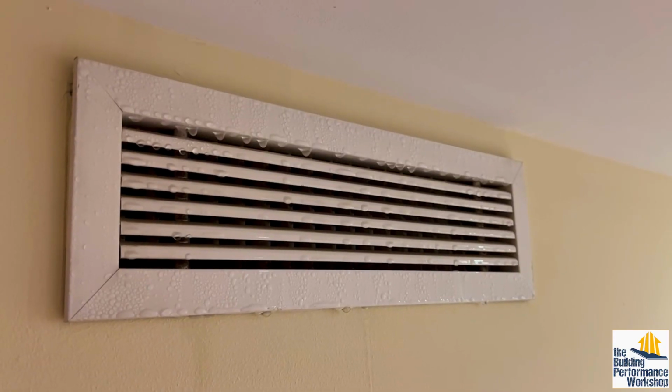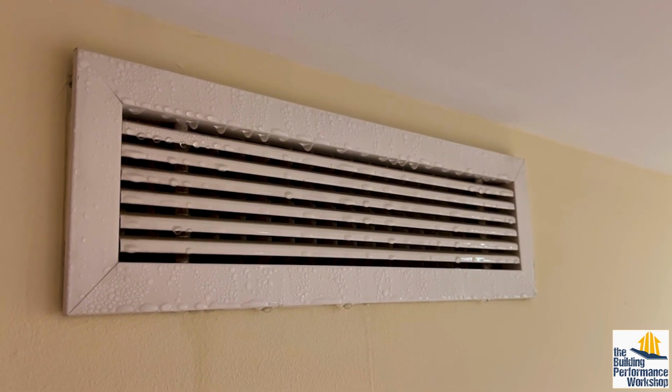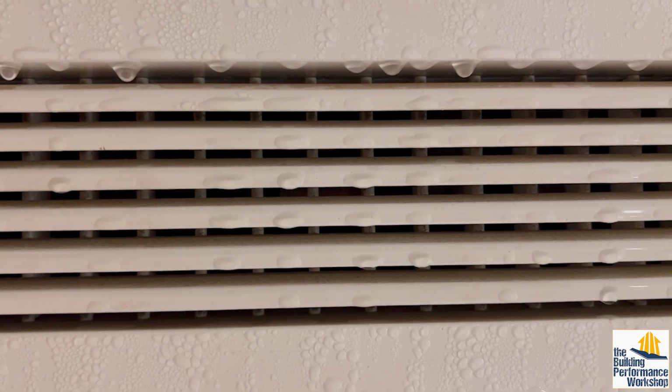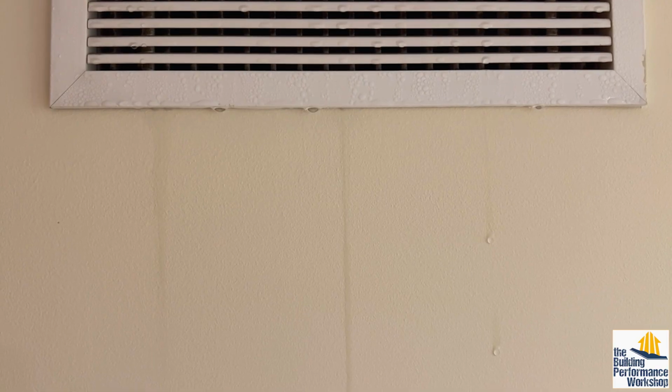Also, you can't do this. If we only run half of the air conditioning in this apartment, then we get major condensation issues, because now we've made the temperature and the humidity level in the apartment two different things. And that is going to result in major wetness dripping off of the vents in the ceiling. That means you get it on your face and on the floor, but on the walls, it means you're going to get these streaks, and it's disgusting.